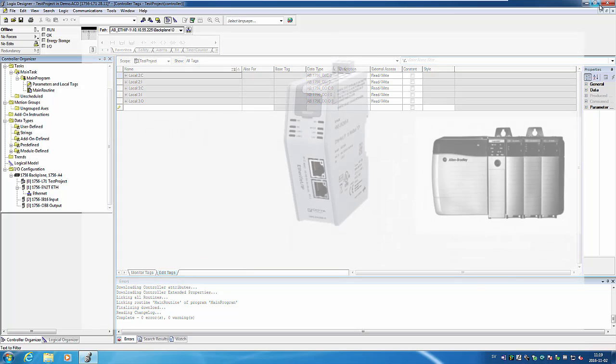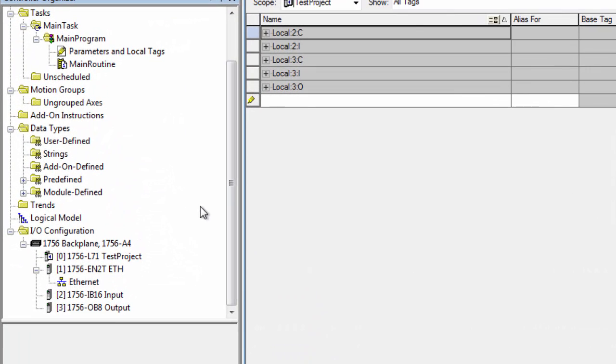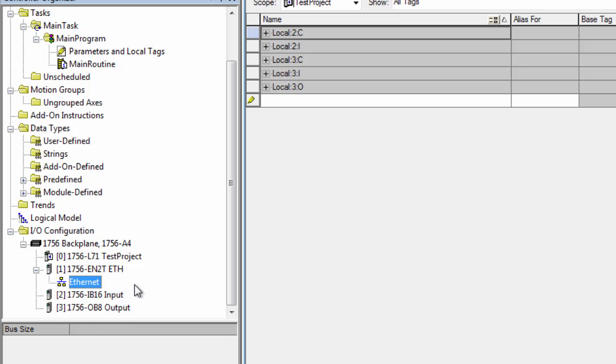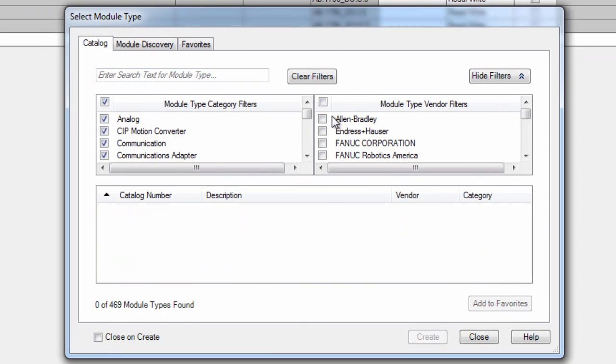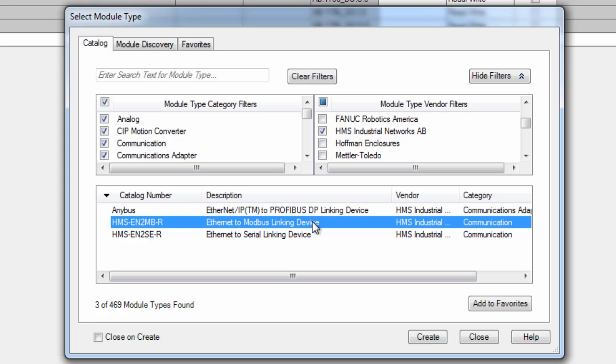I start with the PLC side, that is the communication to the Rockwell ControlLogix PLC. I want to add the linking device in the Ethernet interface so I right-click Ethernet and select New Module. I find HMS Industrial Networks in the vendor list and I can see that the Ethernet to Modbus linking device shows up. So I select this and click Create.